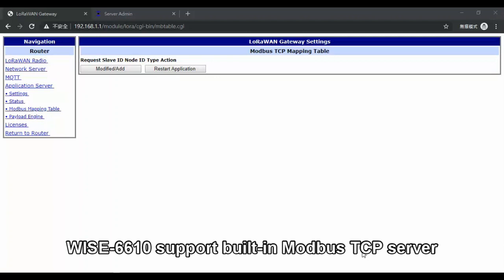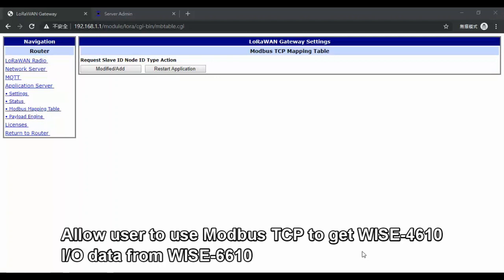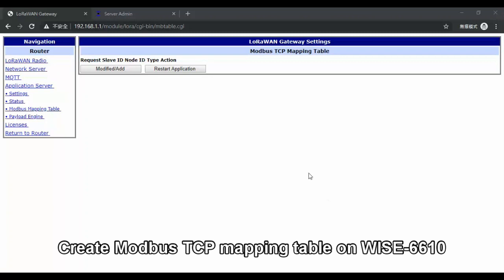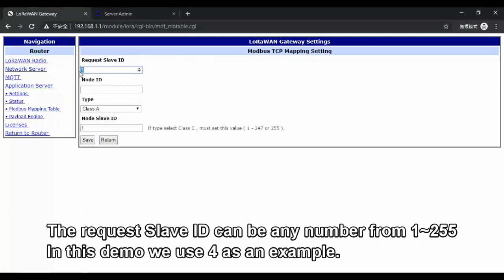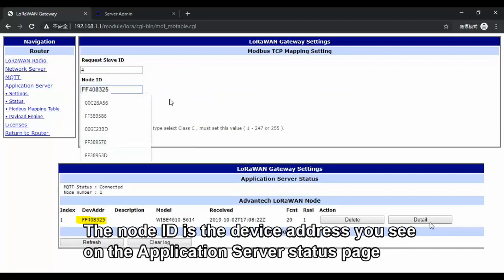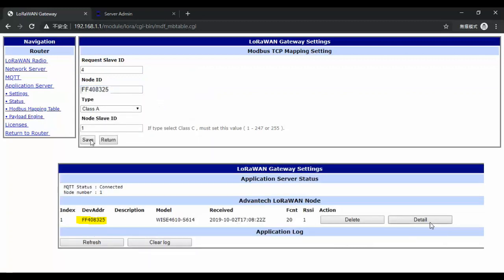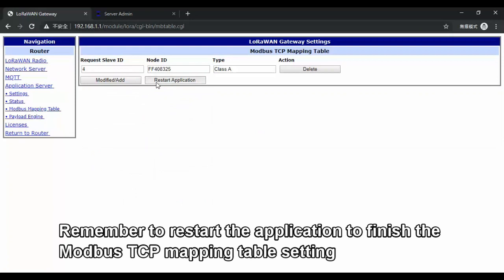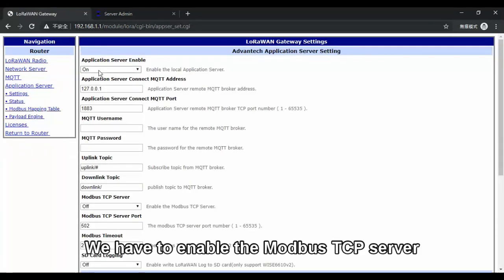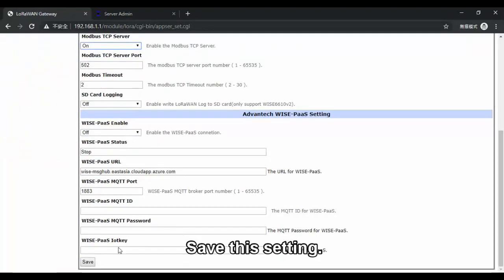WISE-4610 supports a built-in Modbus TCP server, which allows users to use the Modbus TCP protocol to get WISE-4610 IO data. So we have to create the Modbus mapping table here. The required Slave ID can be any number you want — for example, we use 4. The Node ID is the device address you see on the Application Server status. Click Save. Remember, you have to restart the application. After that, we have to enable the Modbus TCP server. Click Save.